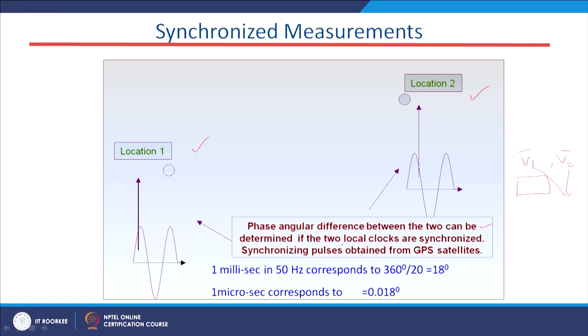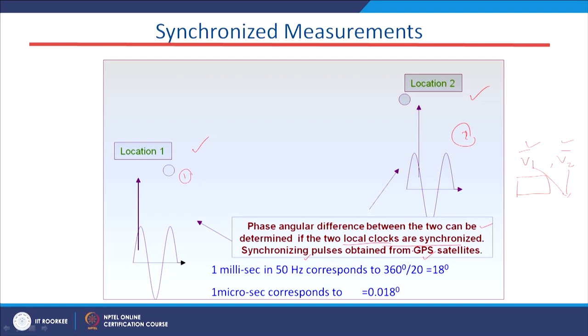This synchronization work is done in WAMS technology using the PMU device. The angular difference between two locations can be determined only if the two local clocks are synchronized. Each location has one local clock, and if these two clocks are synchronized, the two phasors can be compared — this is the meaning of synchronized measurements. The synchronizing pulses are obtained from the GPS satellite.